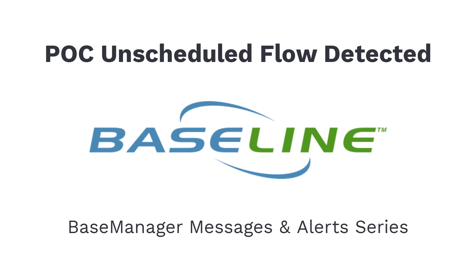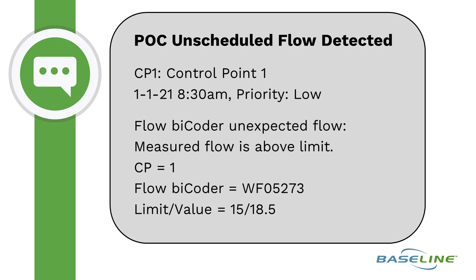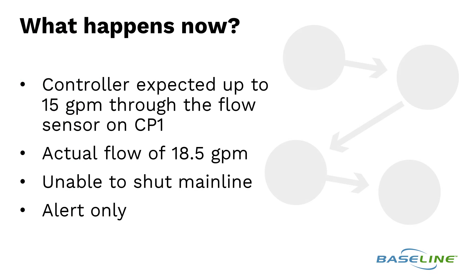POC unscheduled flow detected. The message reads: POC unscheduled flow detected, January 1st 2021 at 8:30 a.m., priority low, flow biCoder unexpected flow, measured flow is above limit. Control point equals 1, flow biCoder equals WF 05273, limit versus value equals 15 versus 18.5.